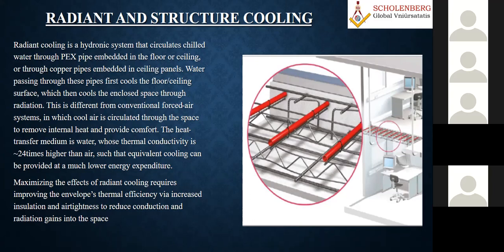They embed these pipes, cooling pipes, chilled water pipes or hot pipes, within the structure above the beam itself. Then it radiates through natural convection, thereby they avoid forced convection. How effective it would be, I don't know, I have not designed it.